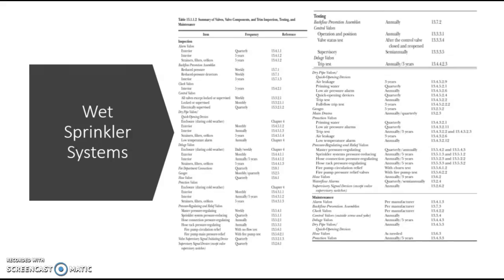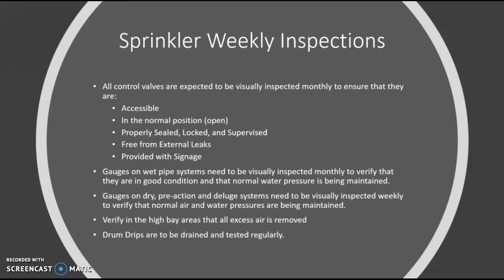The wet sprinkler systems, per NFPA 25, Section 13 has a table where it lists all of the inspections of the quarterly, weekly, monthly, annually, semi-annually testings, which I've got listed here. As you can see, there's inspections from the alarm valves all the way through the check valves, control valves, dry pipe valves, and whatnot. And it actually references the chapters that you can look into to get to this inspection and testing relevance. The sprinkler weekly inspections.